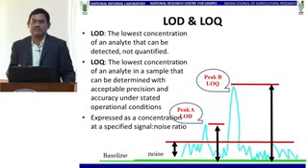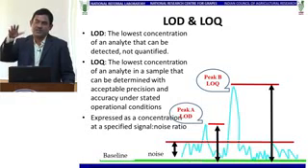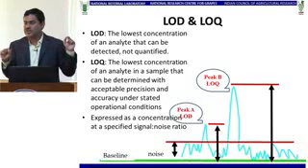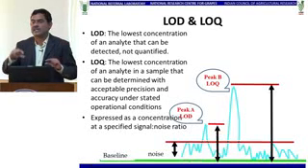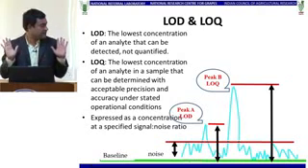Across the world, people calculate the noise and the signal intensity at the lowest level in a solvent standard, pure solvent standard of course. Your signal to noise should be at least 3:1. That is the minimum requirement.